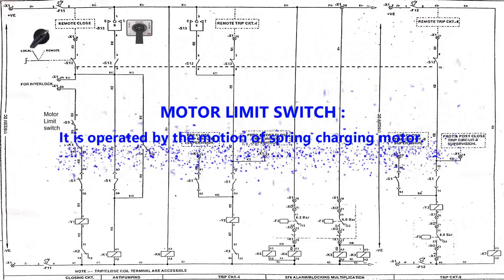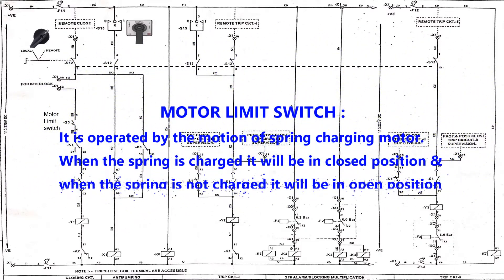Next is the motor limit switch. It is operated by the motion of the spring charging motor. When the spring is charged it will be in closed position, and when the spring is not charged it will be in open position.